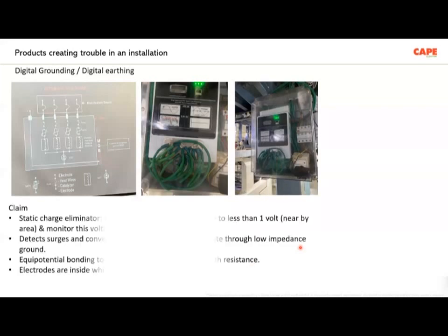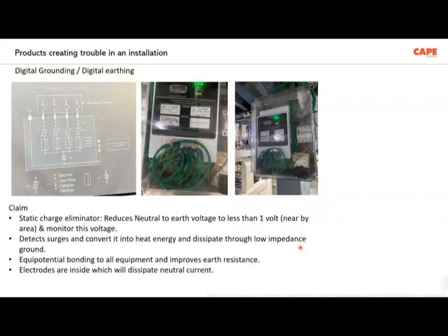The other product which is used, which is actually inviting fire or accident, is called a digital grounding device. This is a new trend in the industry to use this particular device. The manufacturers claim it as a solution for all your problems. They say you don't need earthing, this will absorb fault current, this will absorb neutral current, this will reduce neutral to earth voltage, and all the problems which are faced by the electrical engineer on a daily basis have been solved by this particular product. This is what the manufacturer claims.